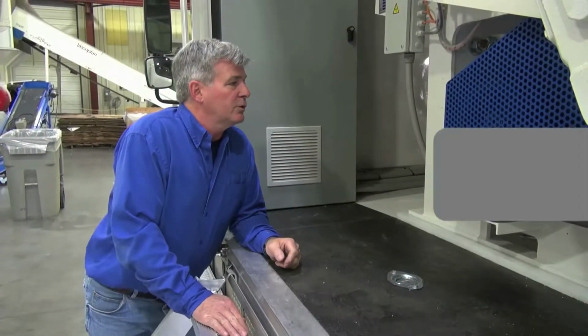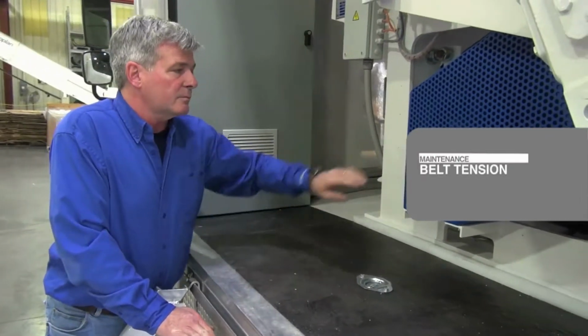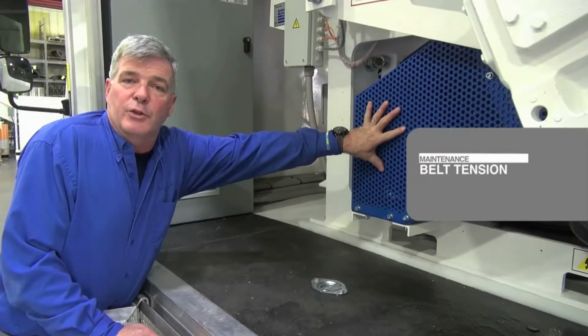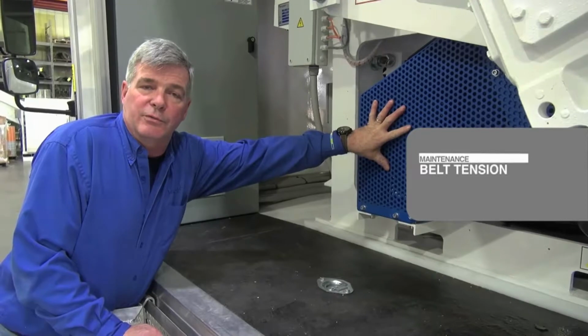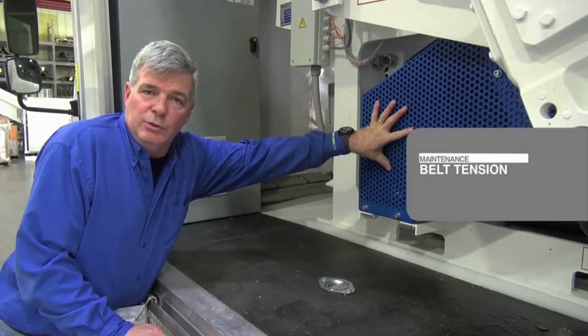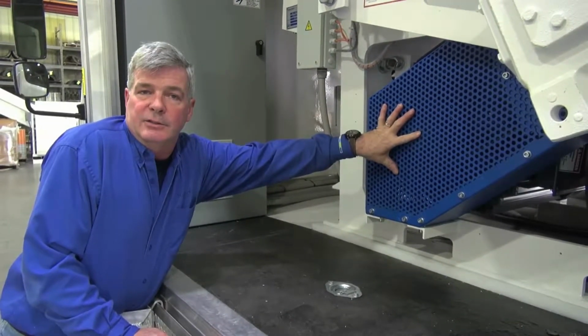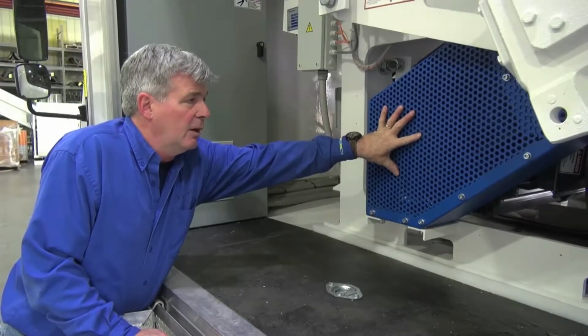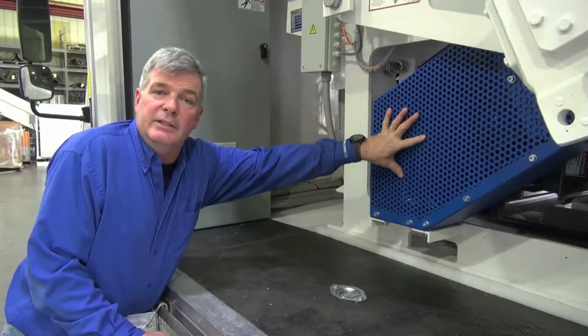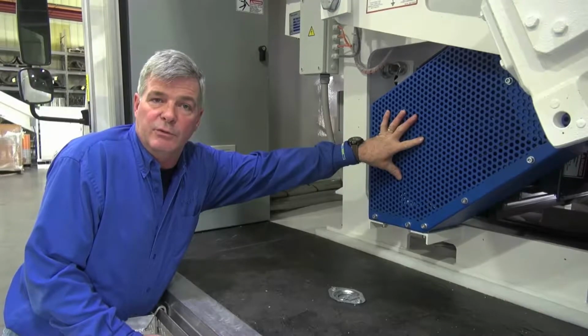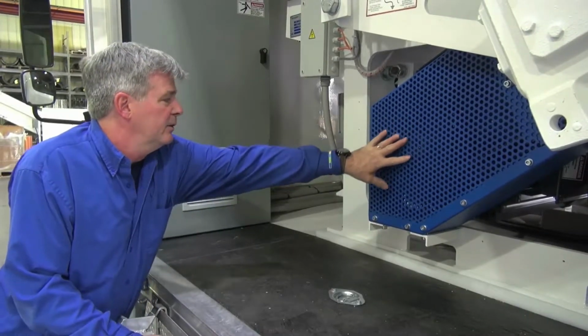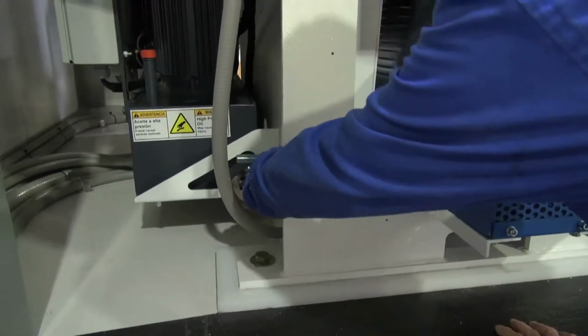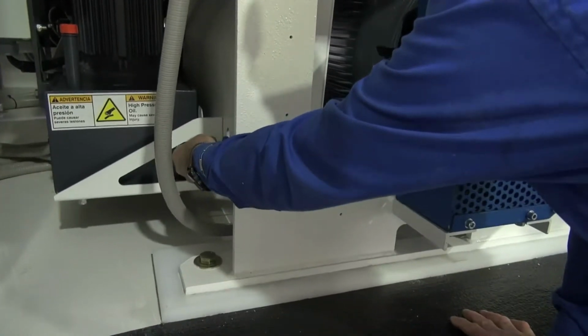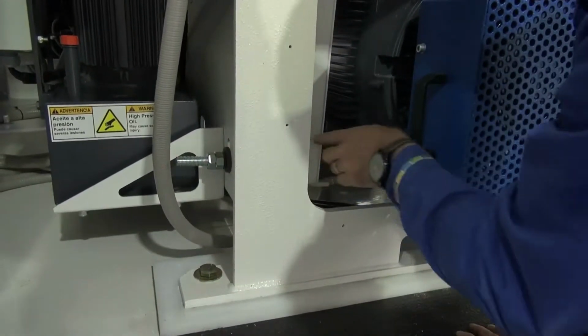Belt tensions should also be checked fairly regularly. The belt should be tightened to 35 pounds at a 1/4 inch deflection. Belt tensioning tools are available at any industrial supply shop. The instructions on tightening the belt are in your manual and give you a very good picture of how to tighten the belt. The belt tightens via this threaded rod. It's double nutted on the front and single nutted on the back.